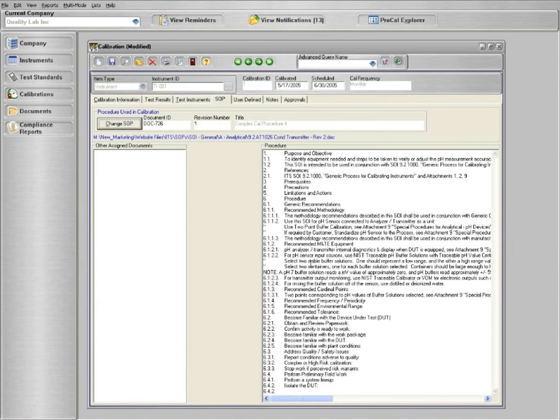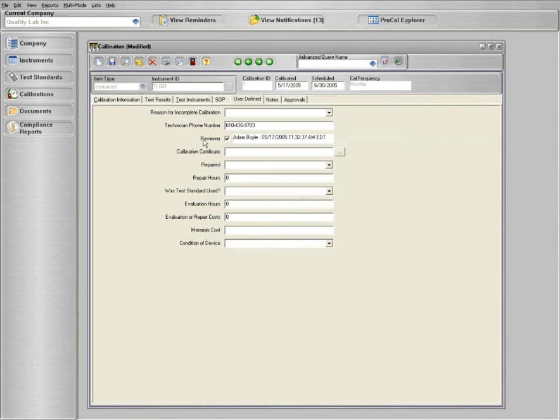For the items that you outsource and you get a calibration certificate back, users may attach the calibration certificate right to the record to document a calibration took place for the asset, rolling the dates forward, as well as managing the calibration certificates if an auditor ever needed to see it.